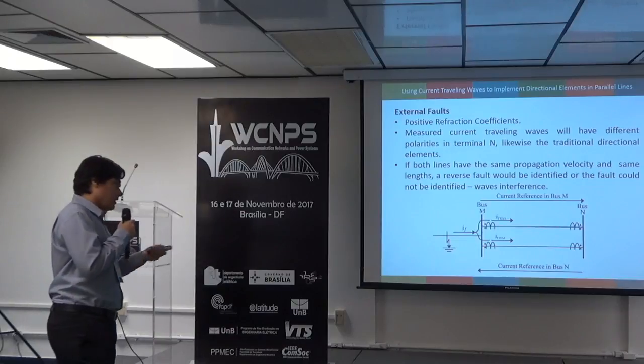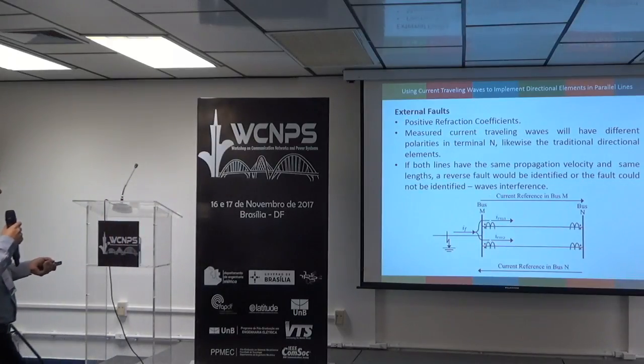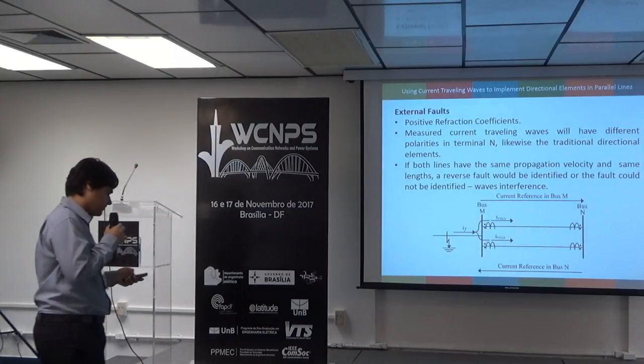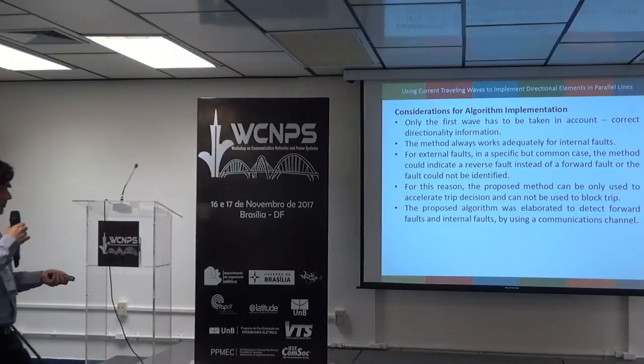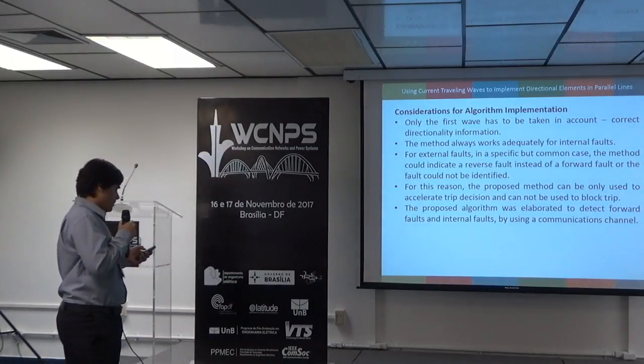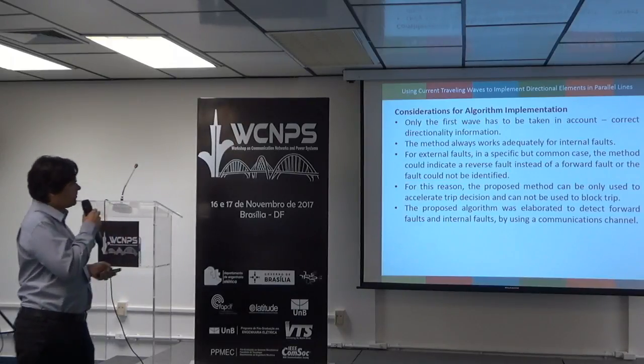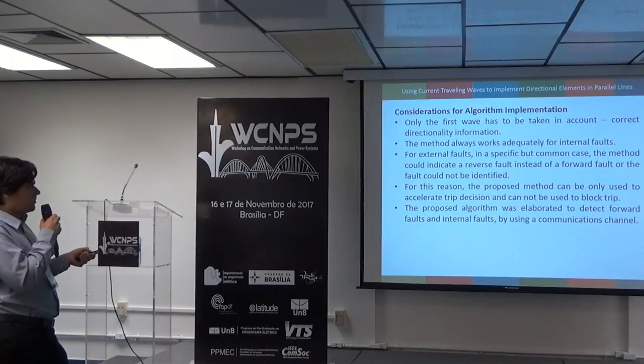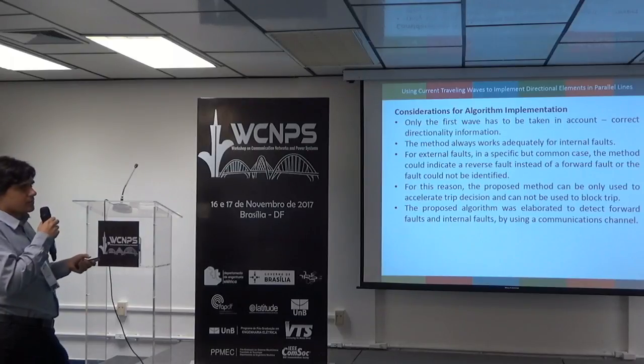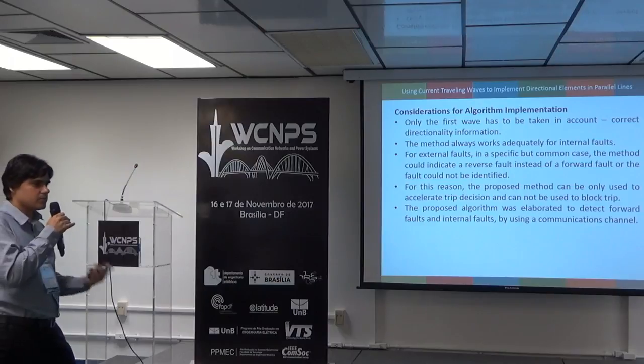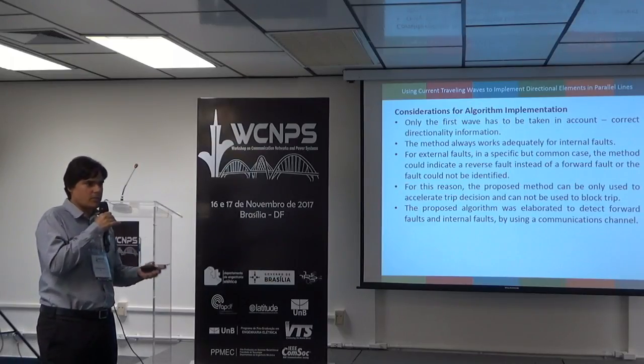But in this case, if both lines have the same propagation velocity and the same length, in a manner that both waves arrive at the same time at bus N, we have a wave interference, and a reverse fault would be identified, or no fault could be identified. In this case, it could not work well. And for implementation, we take it into account. I'll explain later. For the algorithm implementation, we consider only the first wave, because it carries the correct direction information. If you take subsequent waves, the reflections and refractions in the system buses can indicate incorrect directionality.